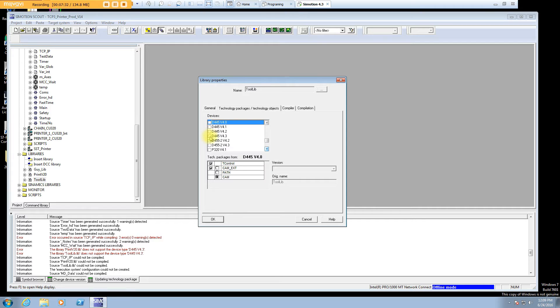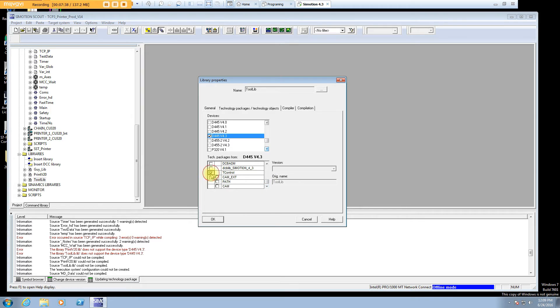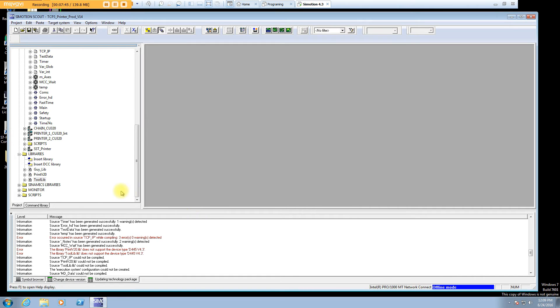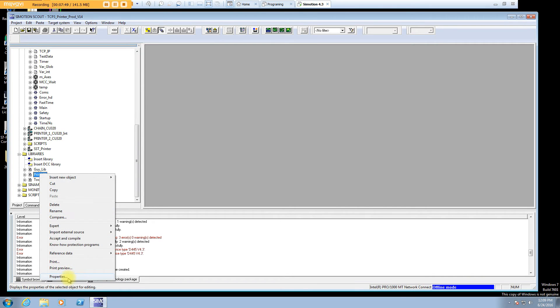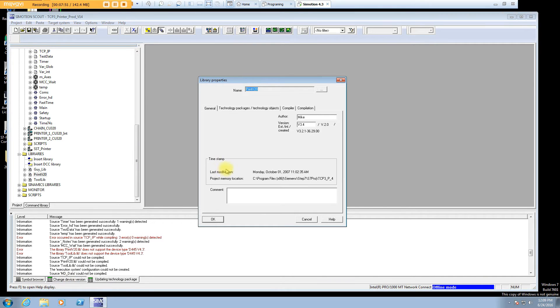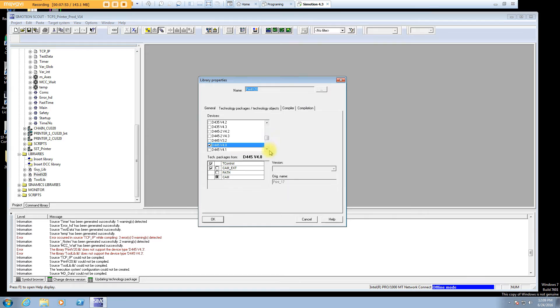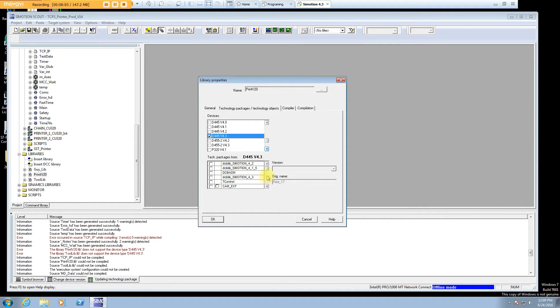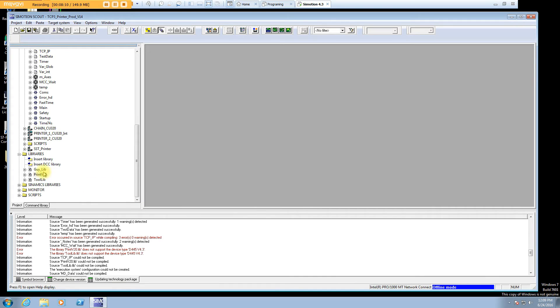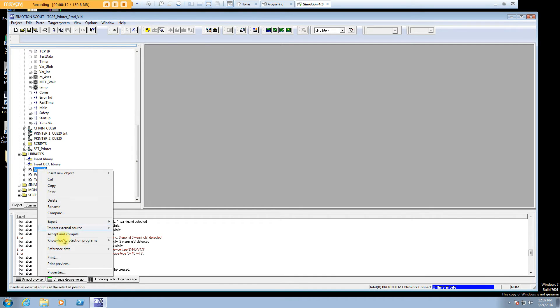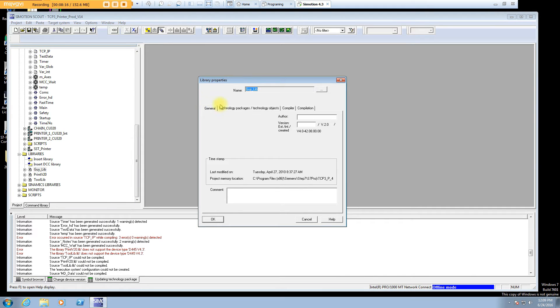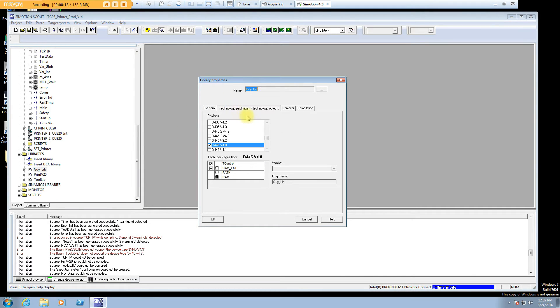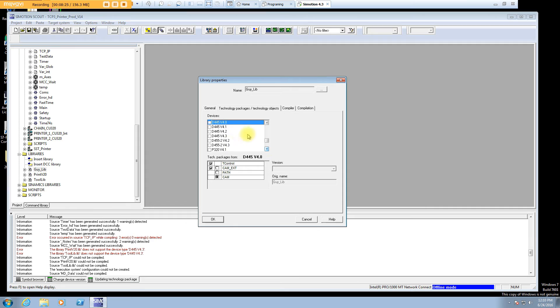But the libraries, you have to select those. So the libraries need to get re-selected instead of the old processor's, the new ones. You need to go to the 4.3, select the same technology packages as it had, but in version 4.3 versus 4.0. Do them all. I notice sometimes that on the first compile pass, it won't flag all the libraries necessarily. Kind of strange. So you may get additional errors after you correct the first ones, but it doesn't take that long to do a simple compile. You'll catch them through a couple iterations of this. I just happen to know it's going to need all of them changed because I've done this before.